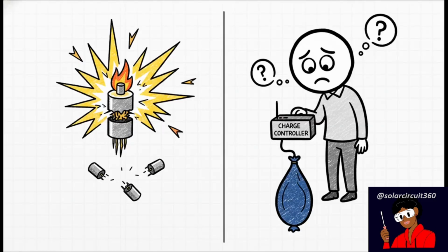And trust me, if you swap these numbers around, you are asking for serious trouble. If you mistakenly use the lower IMP value to calculate your fuse sizes, you'll end up undersizing your protection devices. That means annoying nuisance trips on perfectly sunny days, not to mention major code violations. On the flip side, assuming your MPPT controller will receive ISC all day long leads to wildly inaccurate yield expectations, because the MPPT is intentionally avoiding that short circuit point altogether.